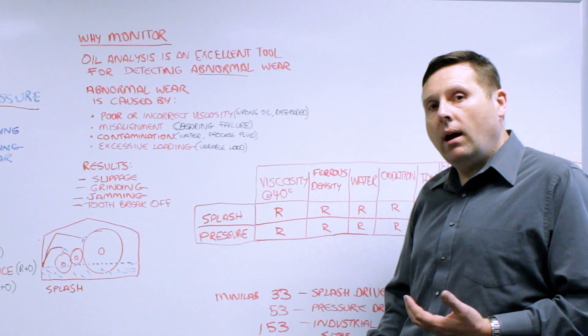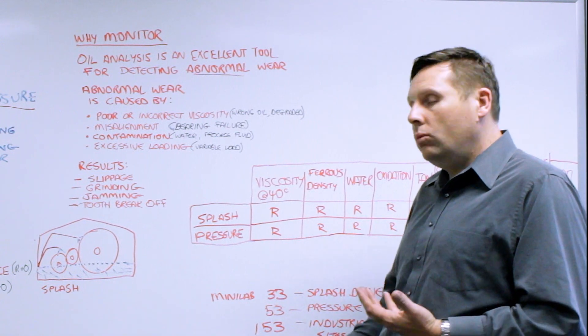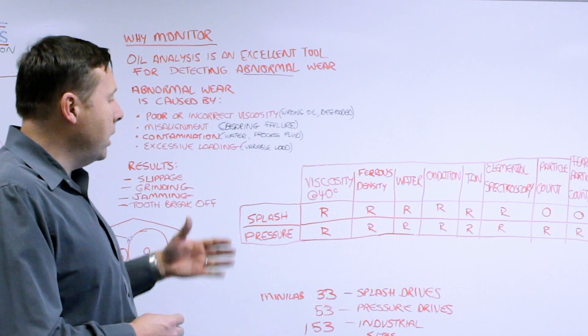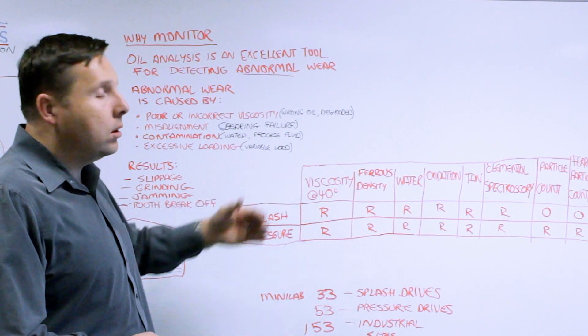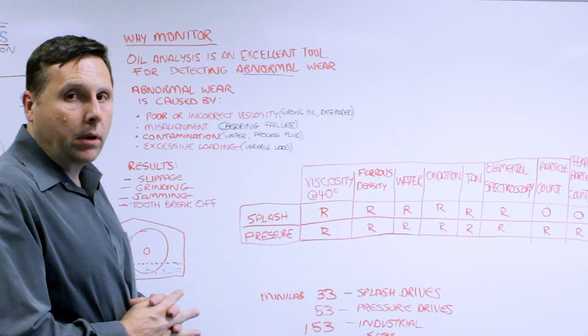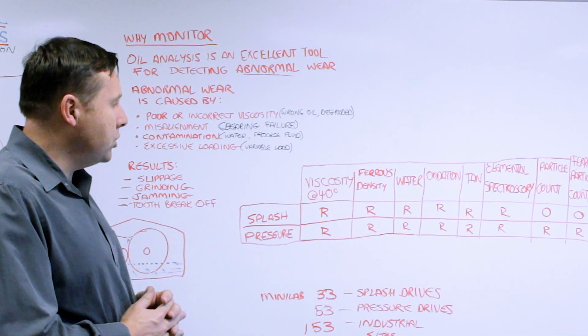So with those two types of application, how do we monitor that from a perspective of oil analysis? Well in all cases we want to look at viscosity. It's the most important physical property of the lubricant so you definitely want to require that for both splash and pressure systems.